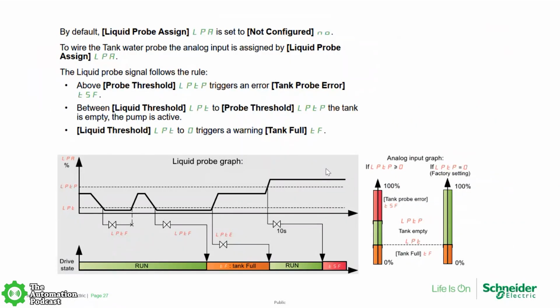So when the tank is empty, when there's a probe error, what the VFD and the pump should do, when the tank is full, low threshold, high threshold, all the configuration is there and available. The idea here, Shawn, is that we have this application as a standalone application. There's no need to add any additional hardware. You can do everything from the VFD and the ATV320 logic inside of the drive and be able to essentially program, configure, work, and do some of these cool application features for the ag and irrigation segment.